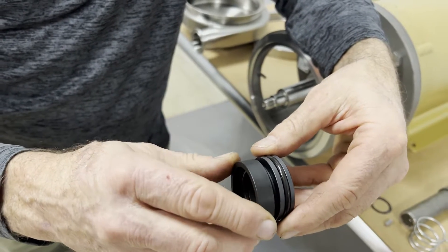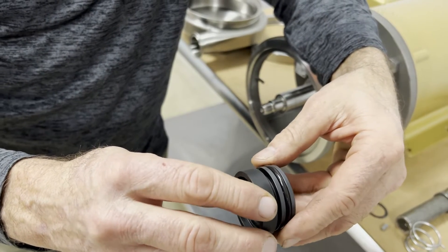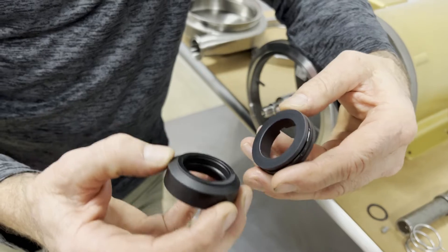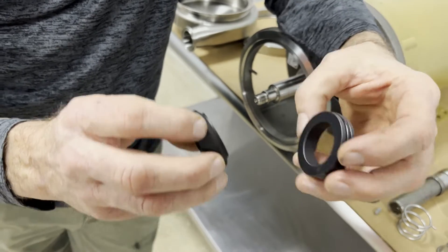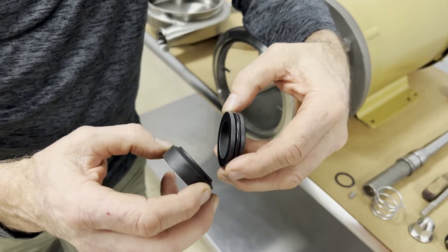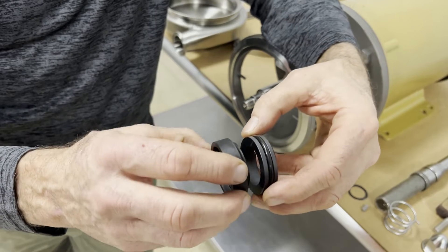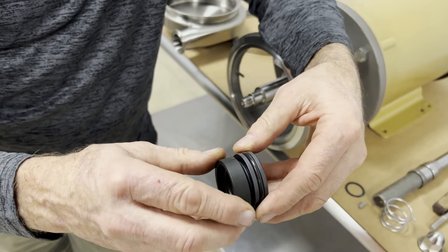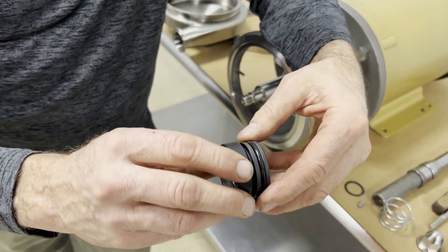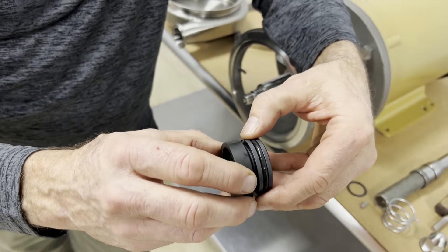Rinse the pump as the pump is running with hot water, preferably, or even cold rinse water, just to get those seal faces clean. The other way these seals fail is when you're pumping hot wort above 200 degrees Fahrenheit. That tends to vaporize on the seal faces and causes them to run dry, so a dry running seal face will eventually wear and cause leakage.